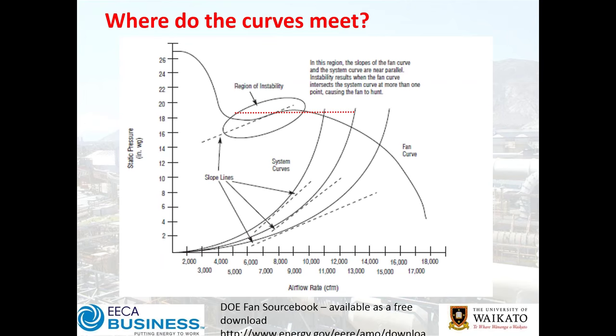From a control point of view, we do not want to operate our systems in this region. In a practical sense, it could be as simple as a change in wind direction outside — a subtle change in static pressure at the corner of the building where your intake filter is. Operators often know when the weather is shifting because they can see it in the plant. When a weather change comes through, it impacts the plant, and if the system is operating at just the wrong spot, there can be quite a shift.